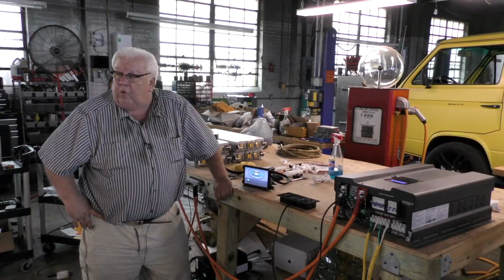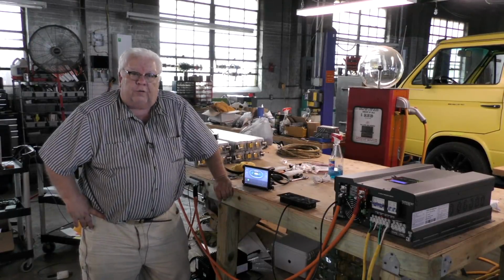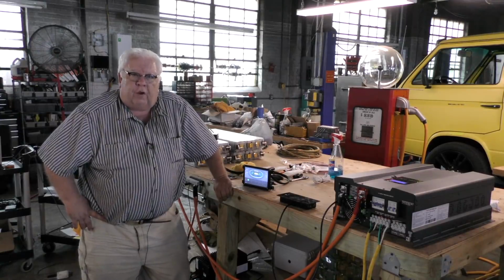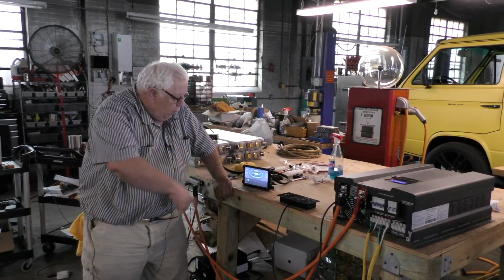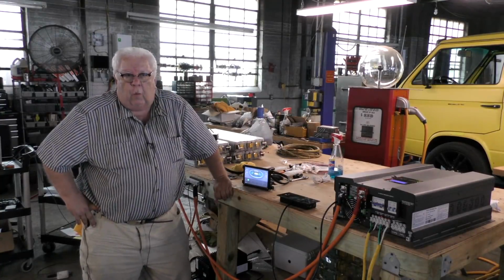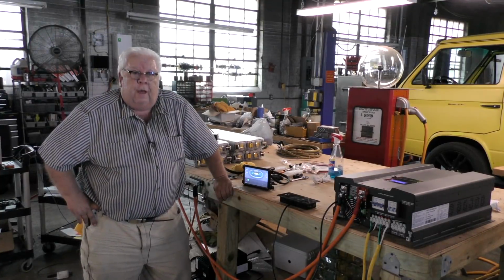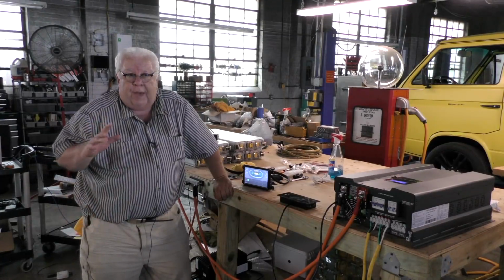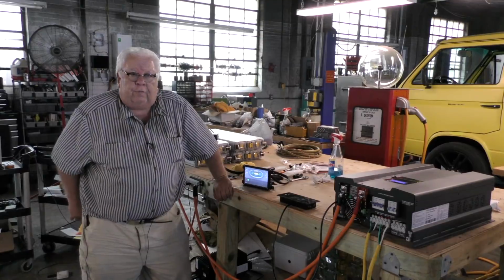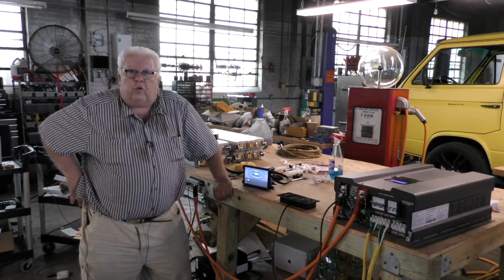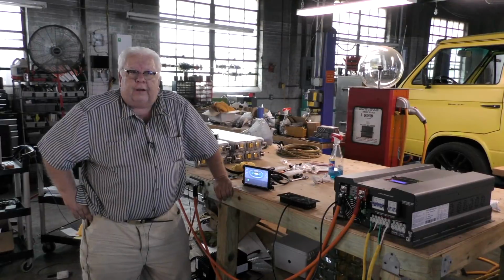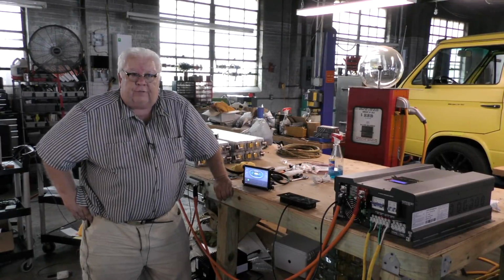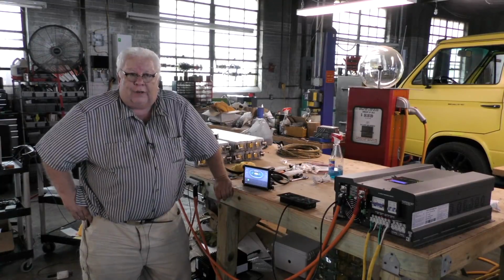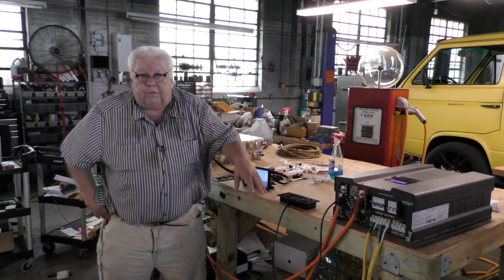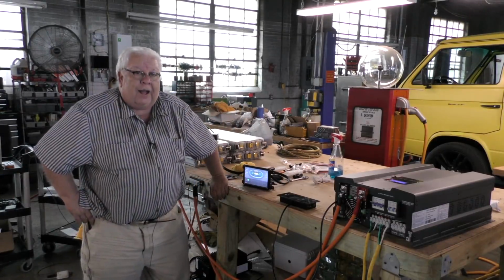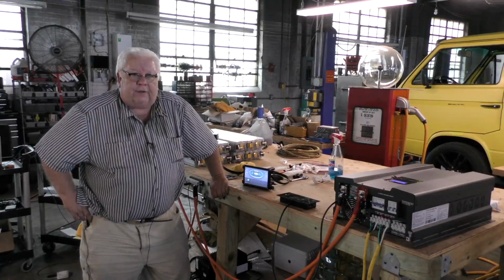And I've had this up to 230 amps of charge, 13.5 kilowatts of charging power coming in through the inverter into the batteries, and it's a 12 kilowatt inverter, and it did it for 40 minutes. I finally had to shut it down because the battery was too full. The bad news on this kind of system is you cannot really let the grid-tied inverters continue to run after your battery is full, because you'll overcharge the battery or disconnect it. If you disconnect it, your inverter goes down, the grid-tied inverters go down. Possible damage to the equipment, it's kind of a disaster.